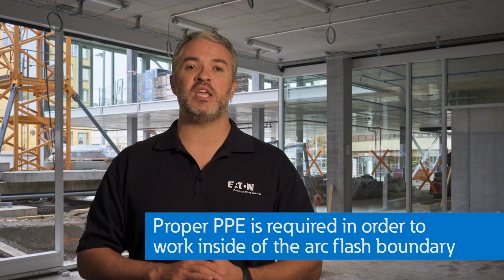For the electrical worker, it's life and death. Even if you say you're going to establish an electrically safe work condition, you need to dress to be able to know whether or not you've established an electrically safe work condition. So arc flash incident energy is all about the electrical worker and going home safely. Working inside this arc flash boundary requires that you are qualified and wearing proper PPE based on the arc flash label.